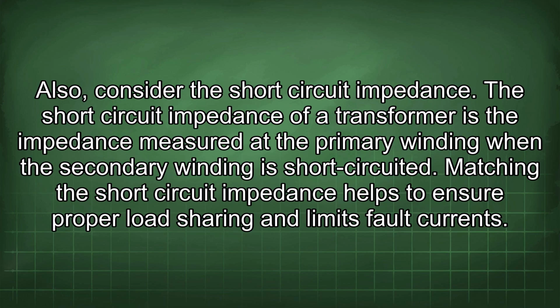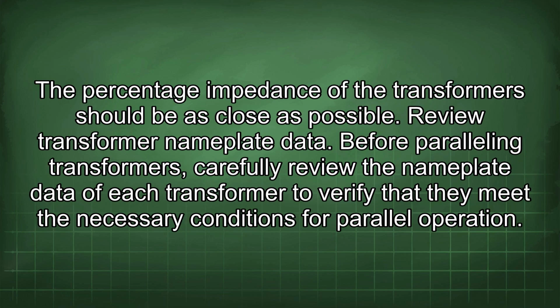Also, consider the short circuit impedance. The short circuit impedance of a transformer is the impedance measured at the primary winding when the secondary winding is short-circuited. Matching the short circuit impedance helps to ensure proper load sharing and limits fault currents. The percentage impedance of the transformers should be as close as possible.